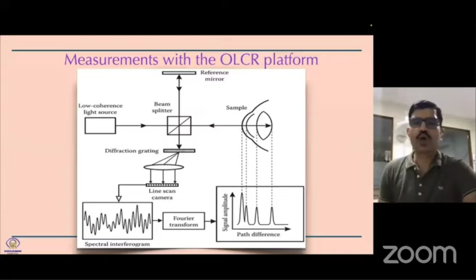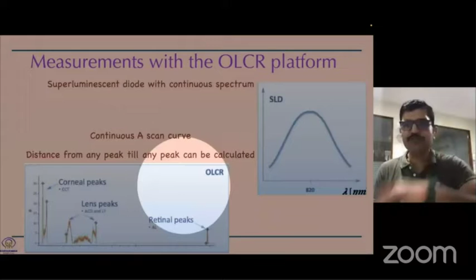The next technology came in, which was optical low coherence reflectometry. Here the design was of a single mirror, but the light source had 830 nanometers of wavelength. The wave that got reflected from the eye was caught by a photodetector device, and it also had a population derived graph already fitted in the machine. Both of the waves went for a Fourier transformation to give us a continuous A-scan curve. Once you get a continuous A-scan curve, you can measure the distance between any 2 points, and it also gives you the whole axial length and the whole keratometry derived from more number of points.